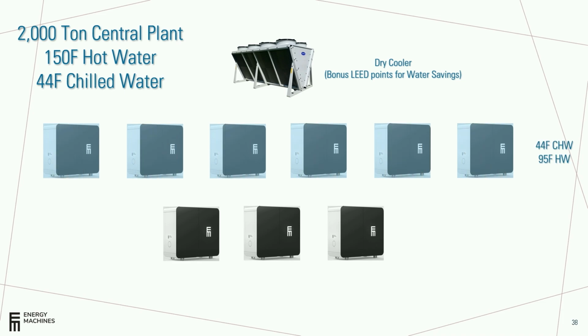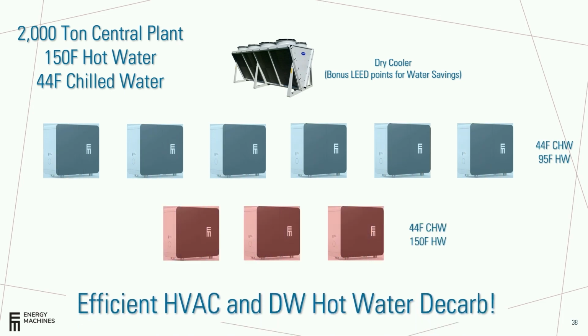So what we did is create subarrays: a cooling-optimized array that hits your typical chiller conditions, and a higher temperature heat pump array that handles space heating and domestic hot water. Once you're getting to 150, you can decarbonize domestic hot water pretty easily. Now you have an efficient HVAC system that's also doing domestic hot water decarbonization.